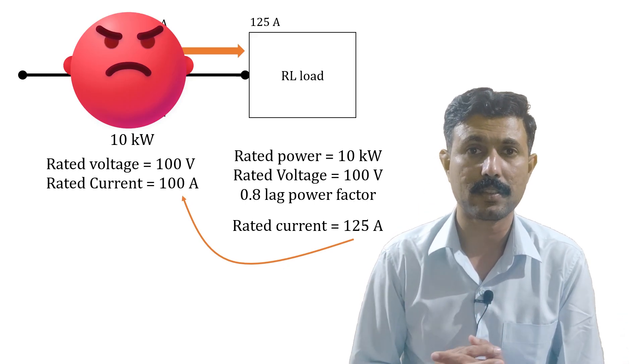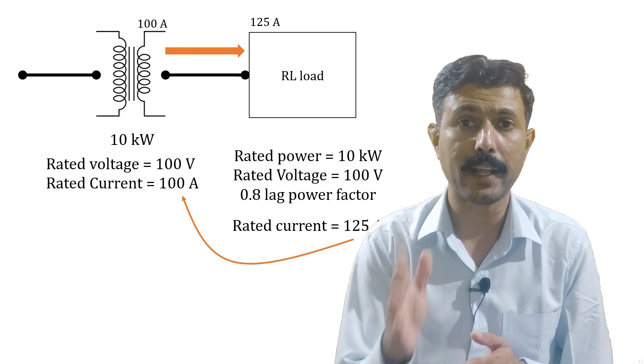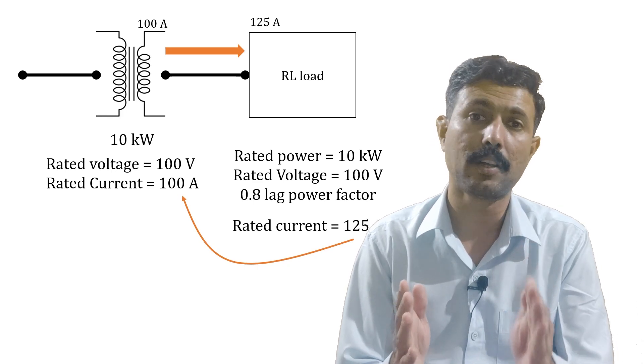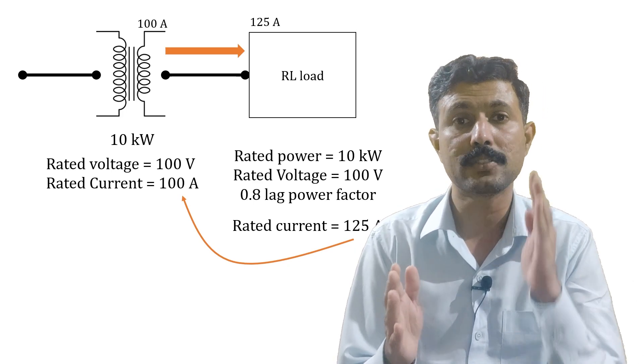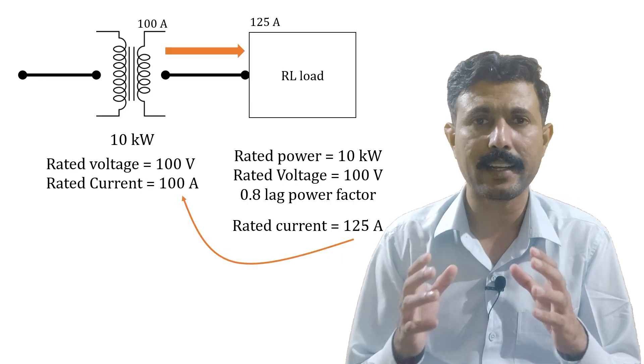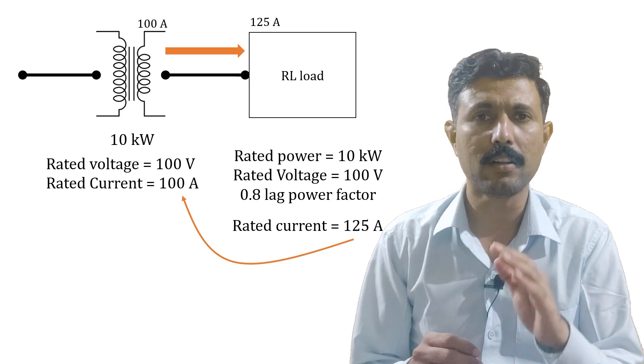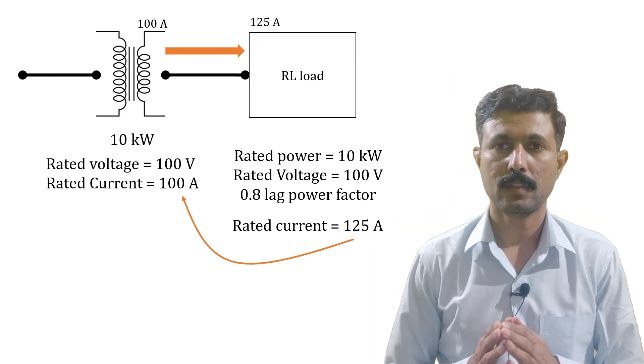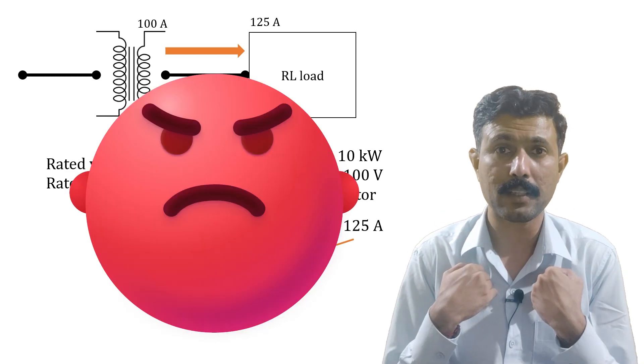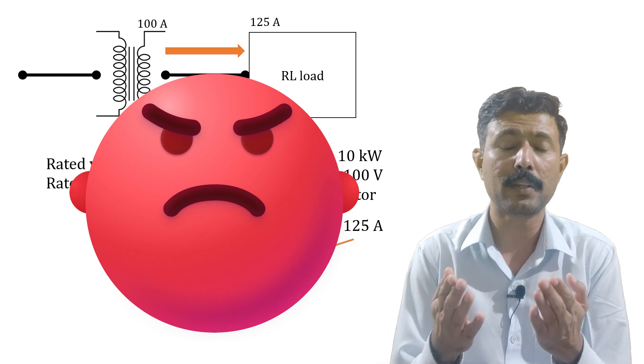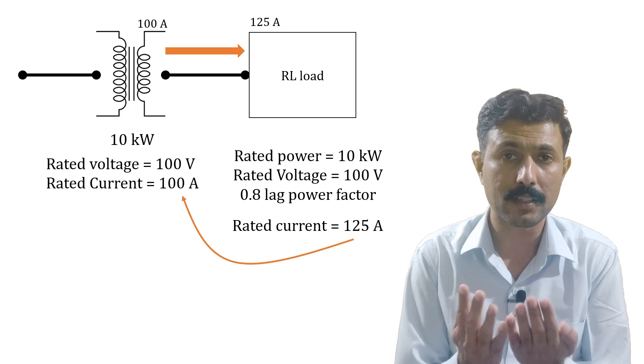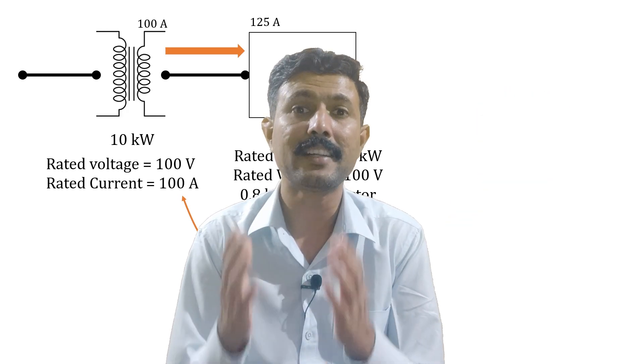This is the disaster: even though the load is also 10 kilowatt, that 10 kilowatt load burns the 10 kilowatt transformer because the current exceeds the rated value. The same thing happens with a capacitive load — it will also burn the transformer. When the transformer burns, the customer gets angry and says: 'You promised me a 10 kilowatt transformer, I connected a 10 kilowatt load, and it burned.' That creates big trouble.